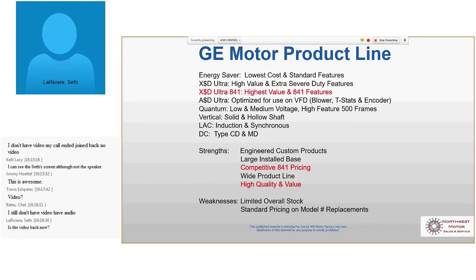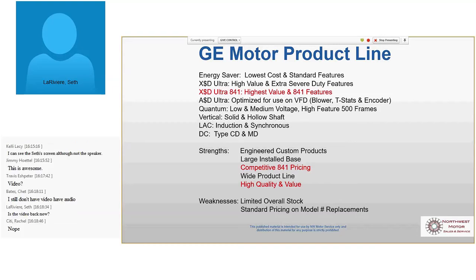So some of the strengths of GE is, they're known in the industry. They pretty much developed the electric motor along with Westinghouse back 100 years ago. So they have a ton of technical expertise. They've pretty much seen every application over the last 100 years. They really excel at making custom motors. So if a customer has a double shaft motor, or if they're asking it to do something unusual from its torque requirements, maybe starting up a really high WK squared inertia blower, that's the kind of stuff that they excel at. They'll do all those calculations.